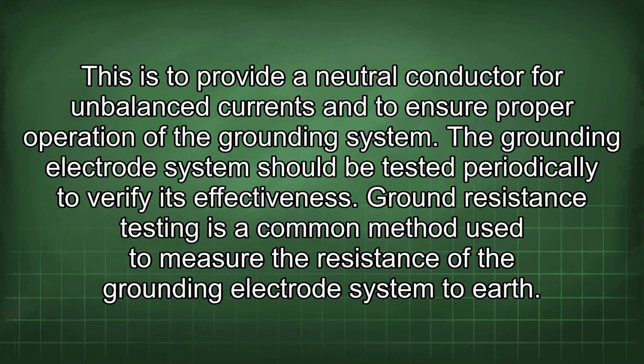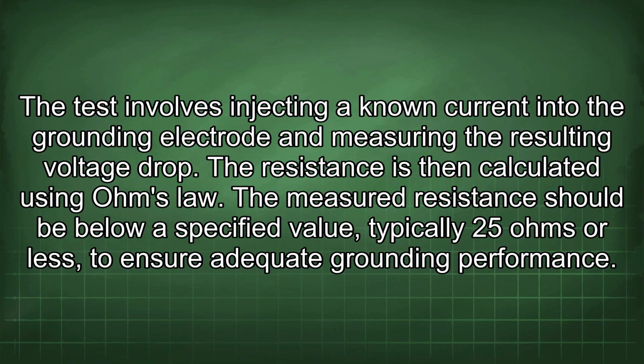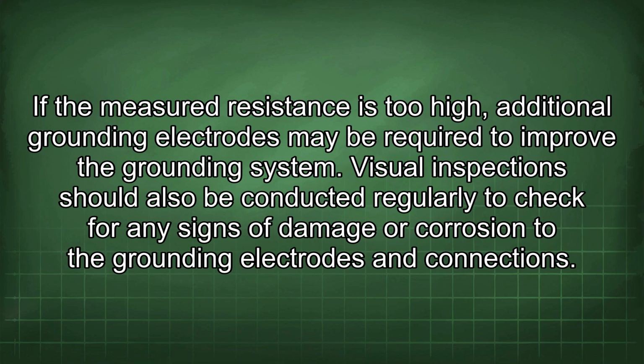The grounding electrode system should be tested periodically to verify its effectiveness. Ground resistance testing is a common method used to measure the resistance of the grounding electrode system to earth. The test involves injecting a known current into the grounding electrode and measuring the resulting voltage drop. The resistance is then calculated using Ohm's law. The measured resistance should be below a specified value, typically 25 ohms or less, to ensure adequate grounding performance. If the measured resistance is too high, additional grounding electrodes may be required to improve the grounding system.